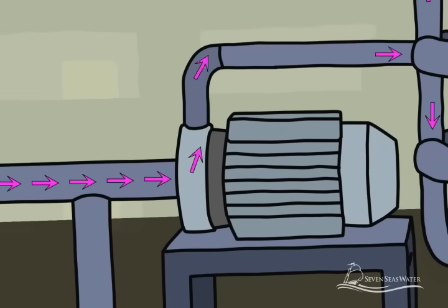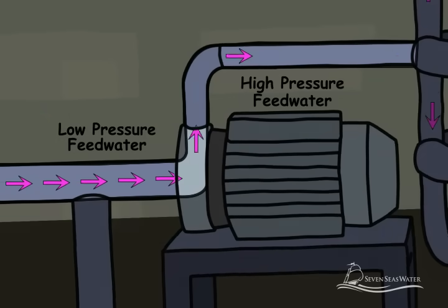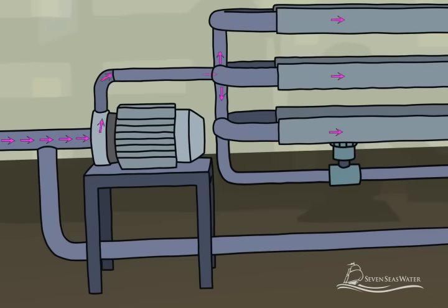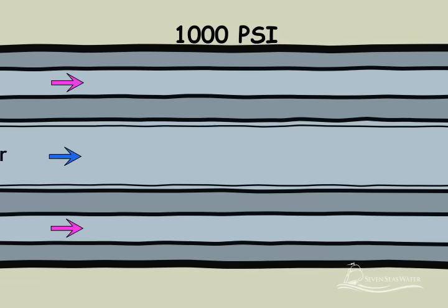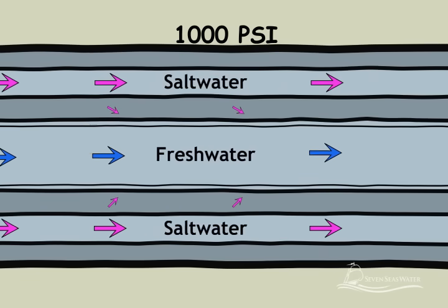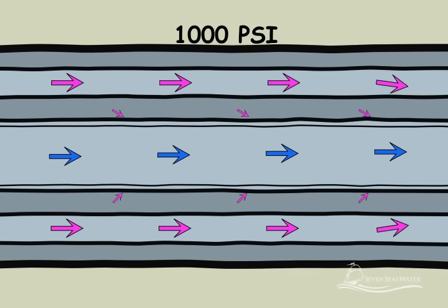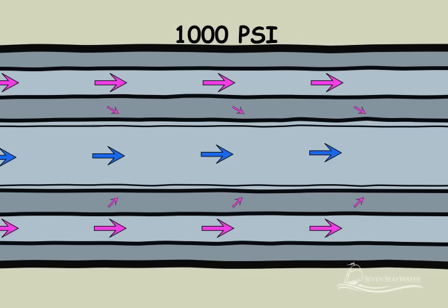High-pressure pumps increase the pressure of the seawater up to 1,000 psi. The pressure needs to be sufficiently high to overcome the naturally occurring osmotic pressure and force water from the saltwater side through the reverse osmosis membranes to the freshwater side.